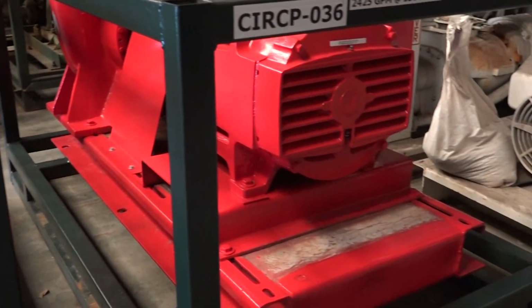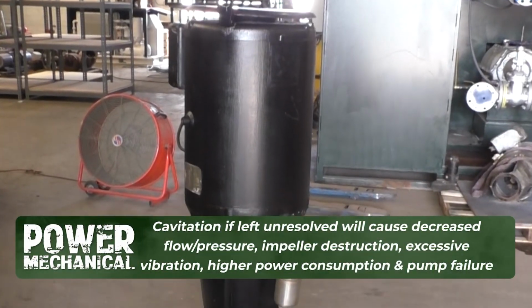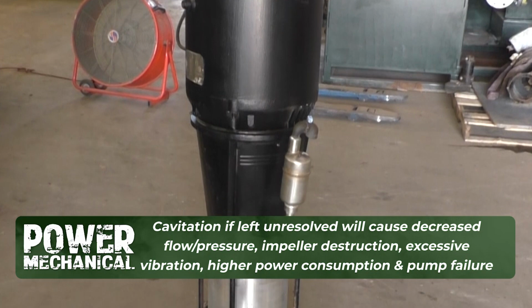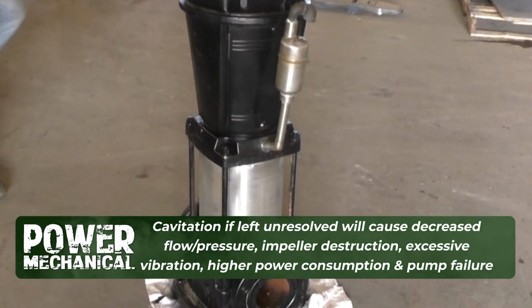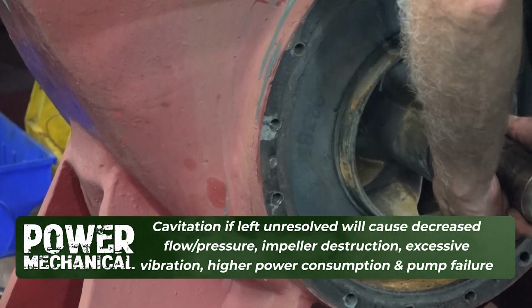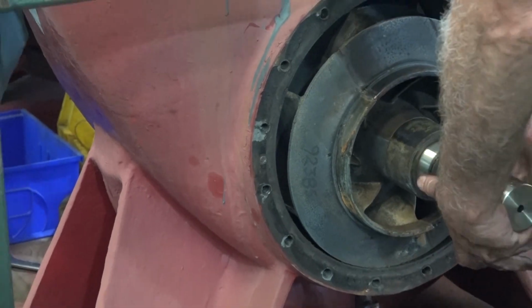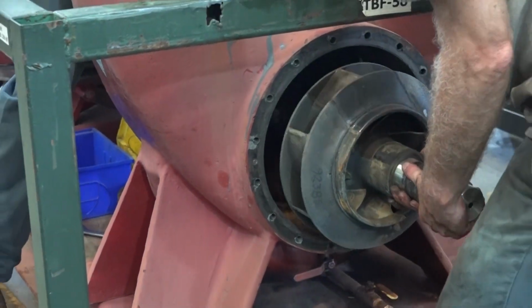Simply put, it's cavitation. Cavitation occurs when water at the suction end of the feed pump turns into vapor in a boiler feed water case caused by high temperatures. As water is entering the pump, it begins to spontaneously boil. Air bubbles rapidly form, and as the water passes from the suction side of the pump into the impeller, then on into the discharge side, the bubbles implode and essentially create a shock-like effect on the impeller of the pump.